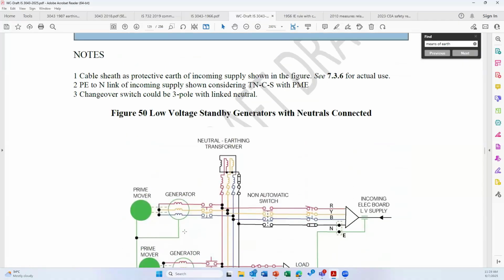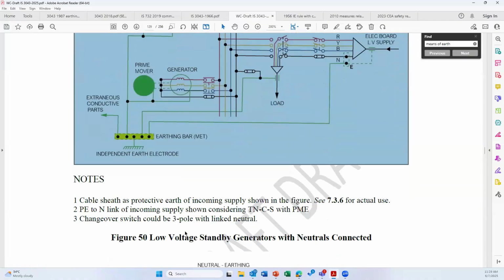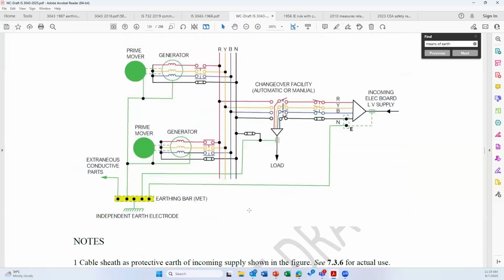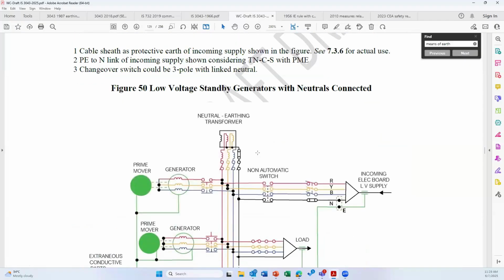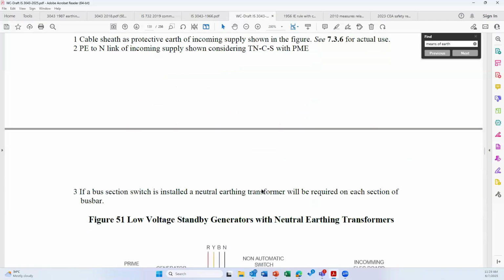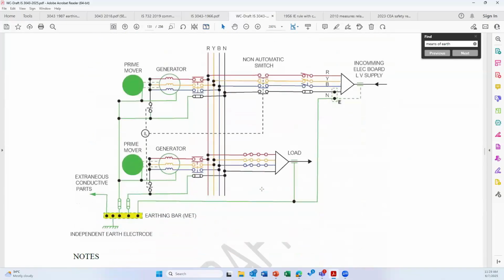Multiple options are here. For example, the first one is, you can see here, a standby generator with the neutrals connected. All the neutrals are interconnected to a common bus bar and the neutral is connected to the earth through one link. The second one is earthed through a zigzag transformer. The third one is the third figure. The next figure is about neutrals earthed through a neutral switching contact. Color pictures are given, which is very, very clear.